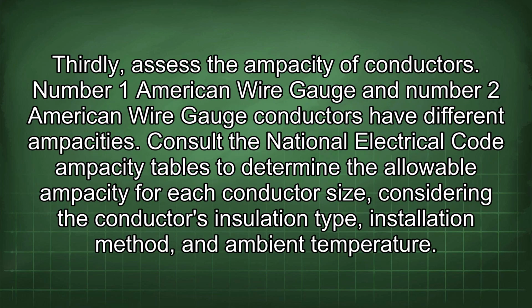Thirdly, assess the ampacity of conductors. Number 1 American wire gauge and number 2 American wire gauge conductors have different ampacities. Consult the National Electrical Code ampacity tables to determine the allowable ampacity for each conductor size, considering the conductor's insulation type, installation method, and ambient temperature.